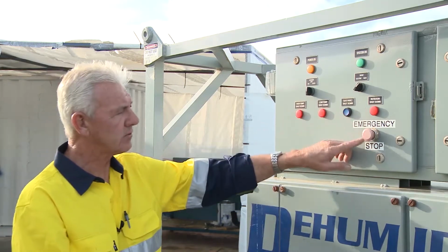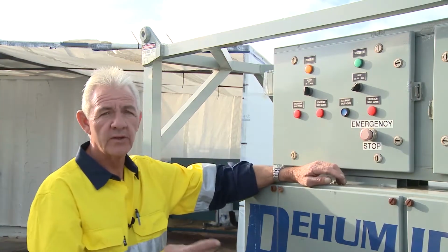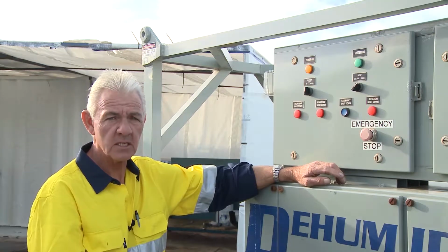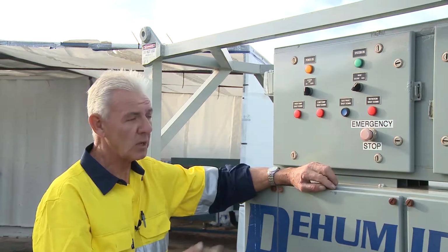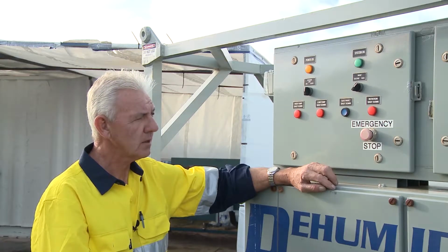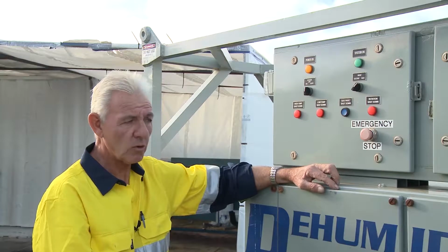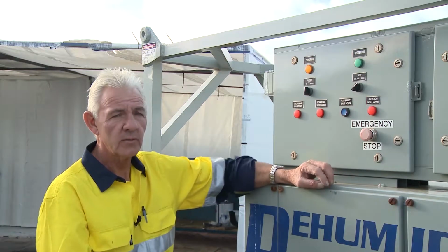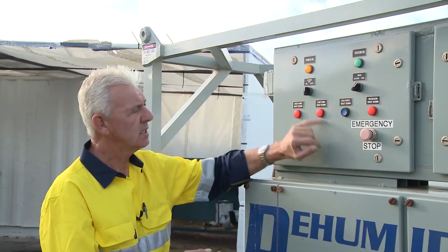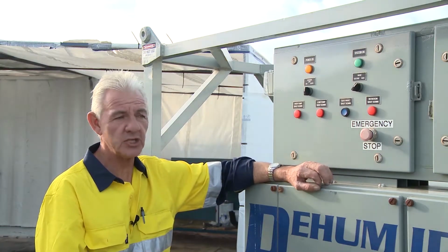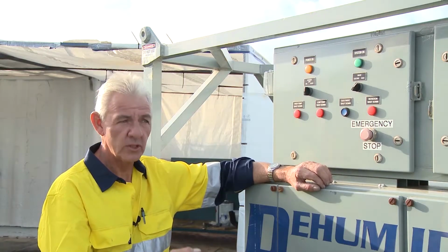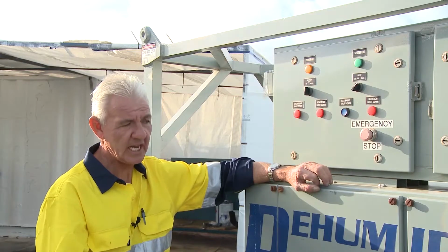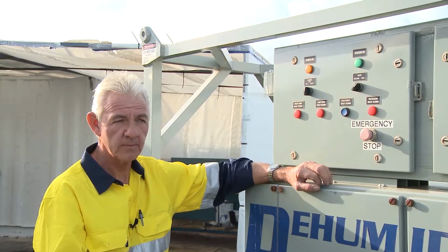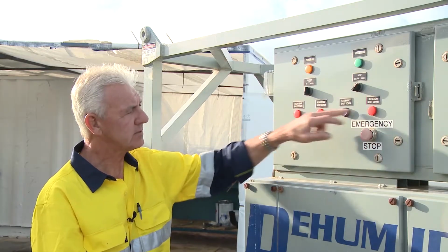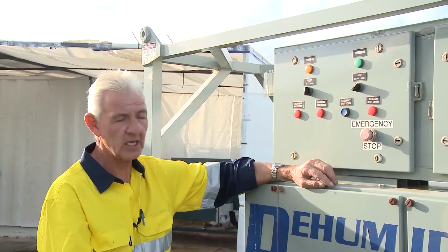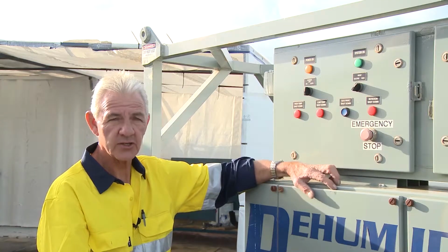The rest of the information on here is, of course, a rotational shutdown. So say, for example, there is a problem with power, it's intermittent. This particular light here will illuminate. The rotational shutdown is primarily because of differentiation in power. So all of these things here are a nomination in relation to how we've set the machine up, basically. So say, for example, your genset runs out of power, you run out of gas, your filters are blocked, you'll start to see the illumination of some of these lights. A gas fault, basically same thing. You've run out of gas, the regulators are dirty.